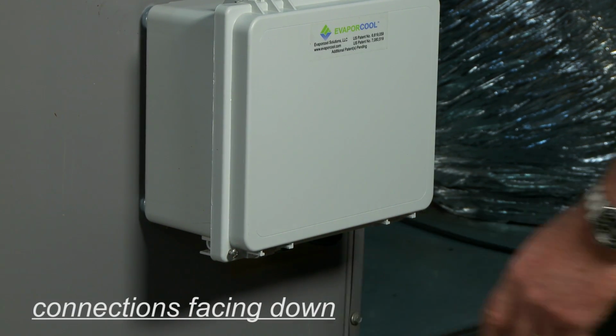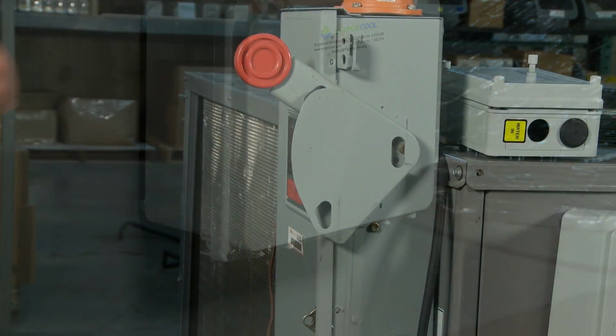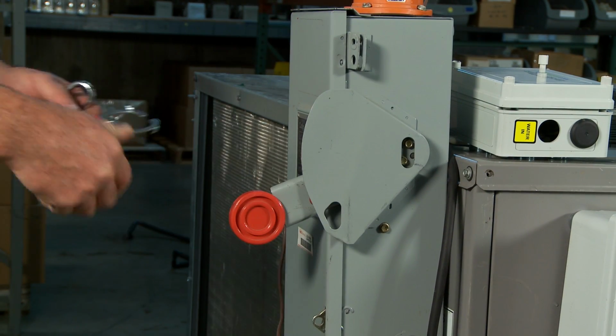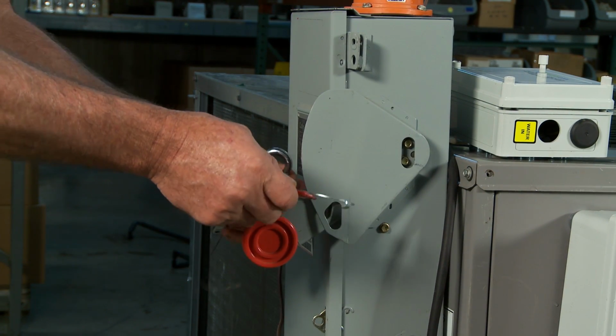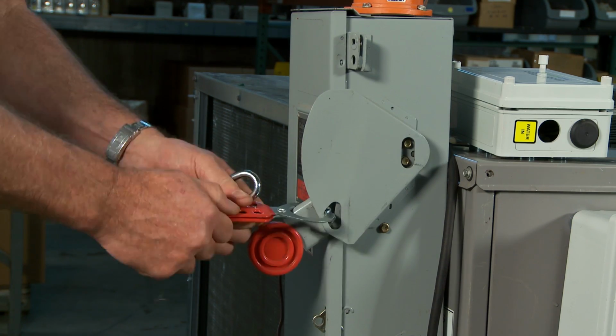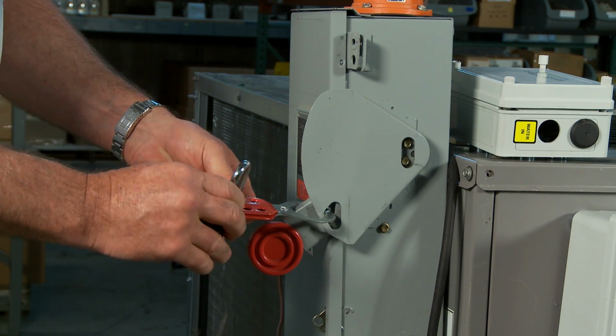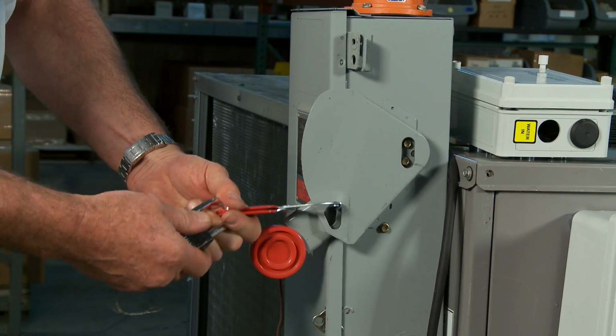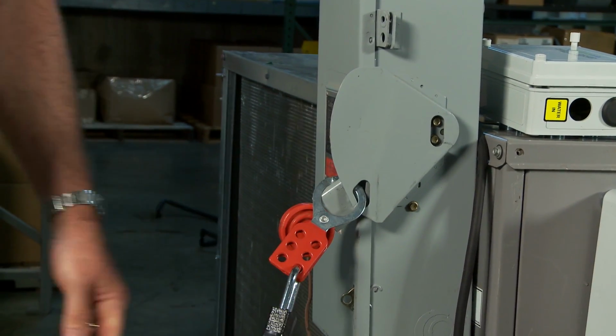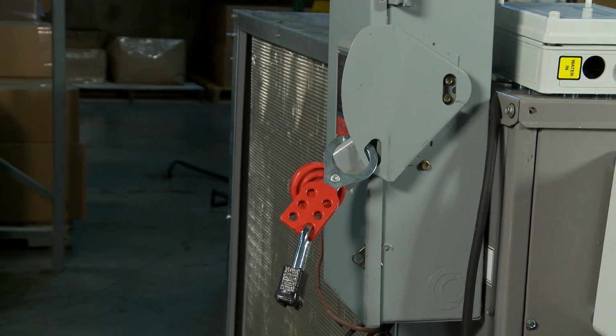Remember, when working on outdoor units, safety is paramount. Ensure no electrical equipment that you will be servicing is connected, and follow all appropriate lockout, tagout procedures. Once you have verified the electricity to the outdoor unit is disconnected, you can remove the hail guards and clean the condenser coils. Follow the instructions of the unit's manufacturer for proper coil cleaning techniques.